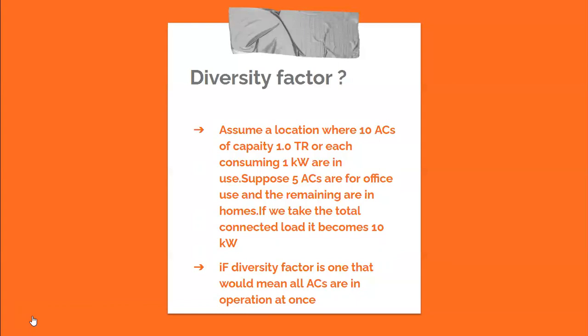Okay, so how much of this load of 10 kilowatt is coincident? That is told by the diversity factor. So when your diversity factor is unity, it would mean that the coincident load is the entire load. So the connected load and the coincident load are the same. Okay, so that obviously is not always the case.